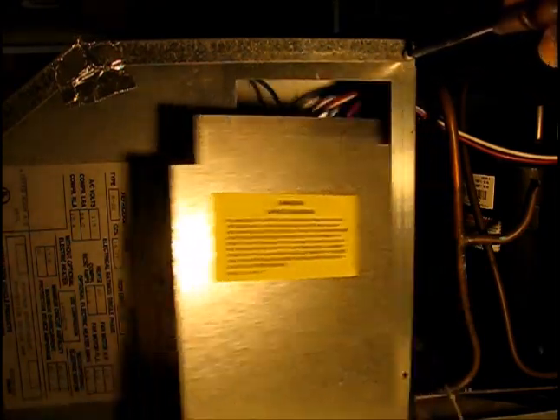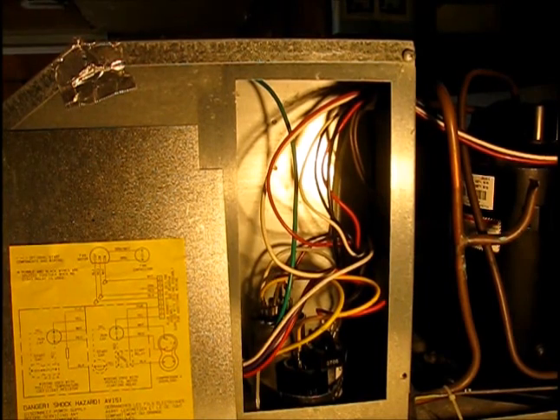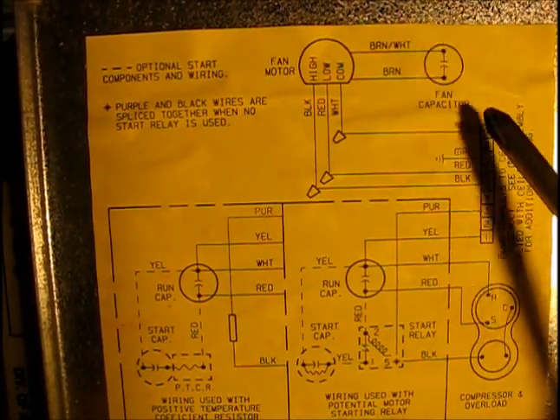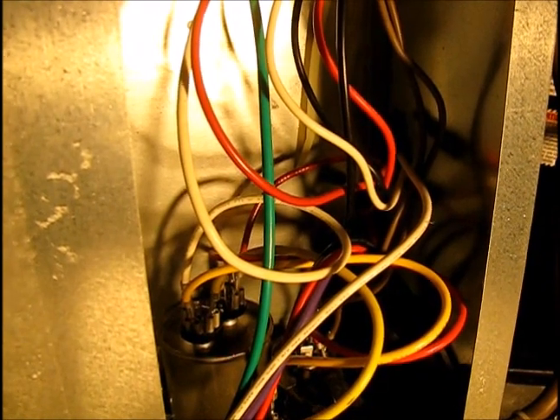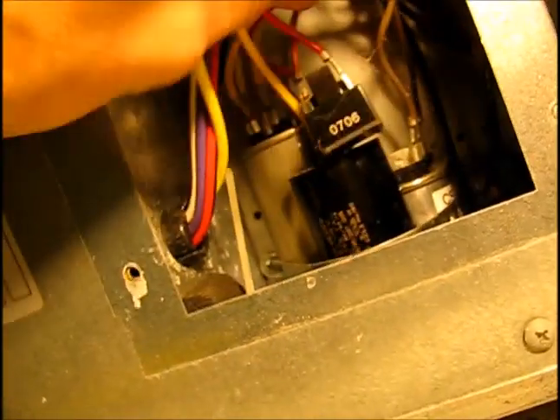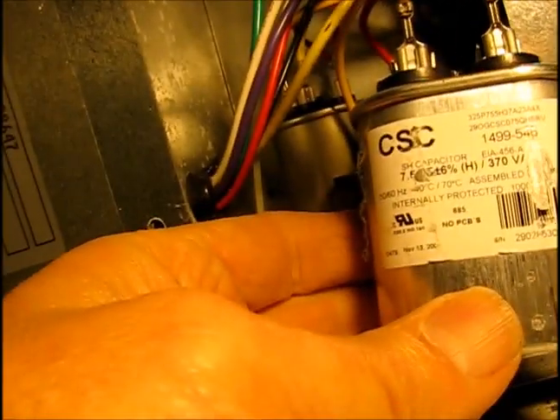Loosen the top one, slide it out, and there's a schematic — and there are our three capacitors. The capacitor we're interested in is the fan capacitor. Brown and white wires go to it. Following the two brown wires that come from the motor down, we go to this capacitor right here. This is the one we're interested in — it's just held in by a strap, so we're going to undo the Phillips screw holding the strap on, loosen it, and there's our fan capacitor.